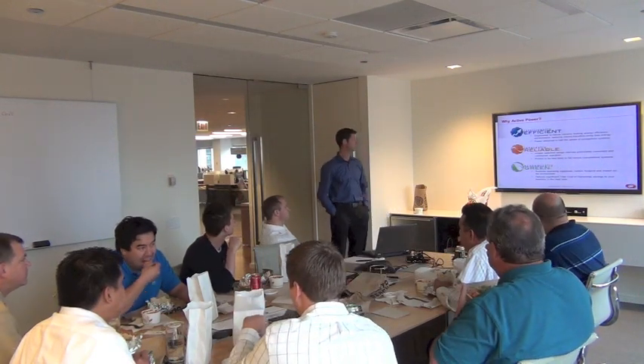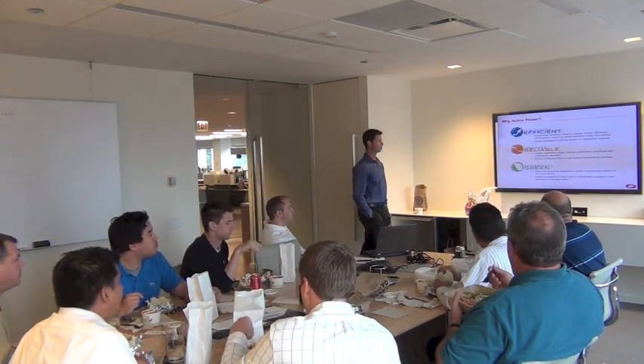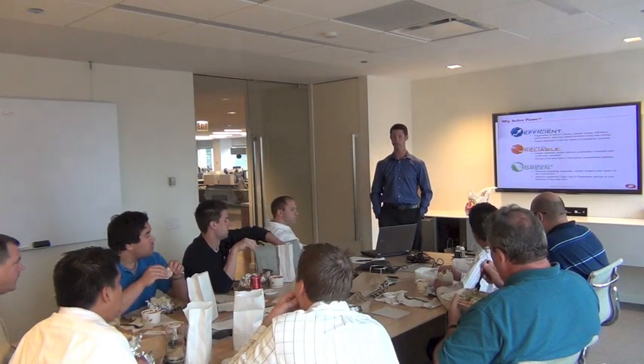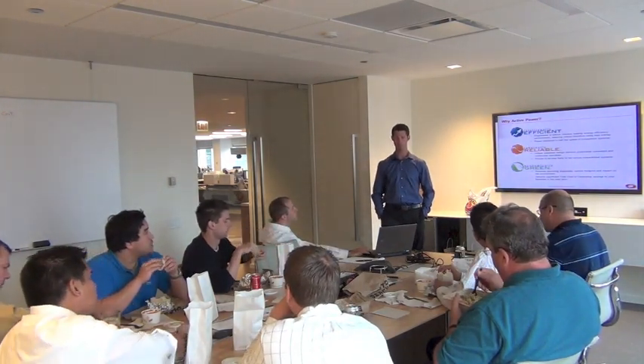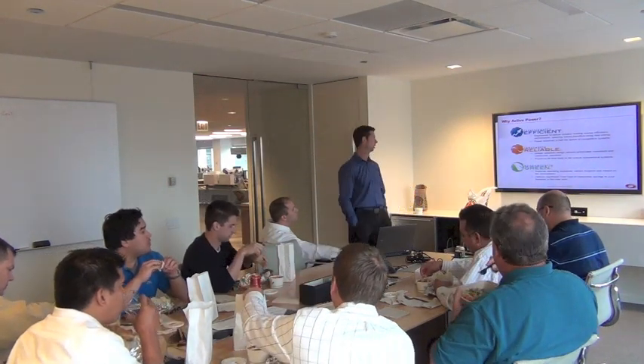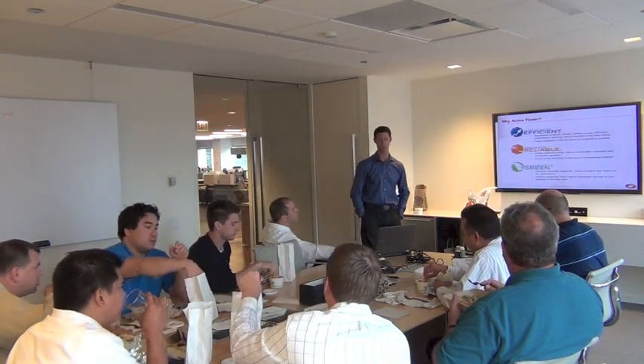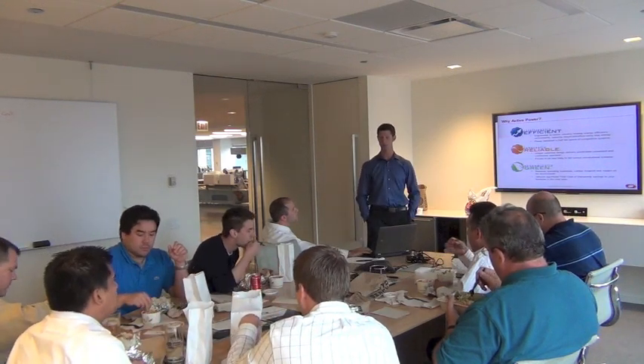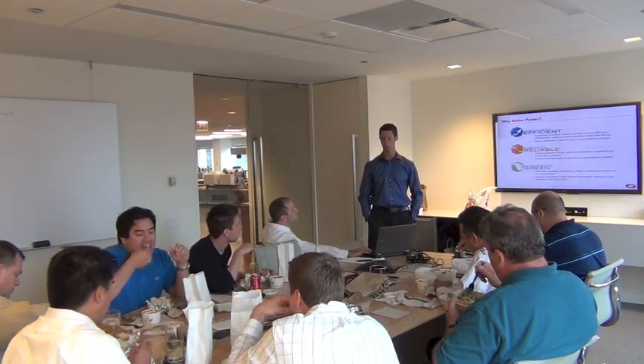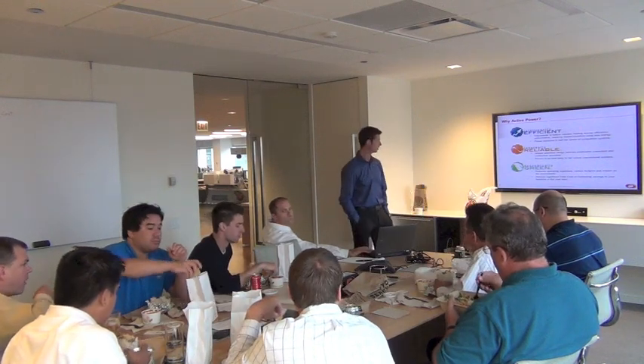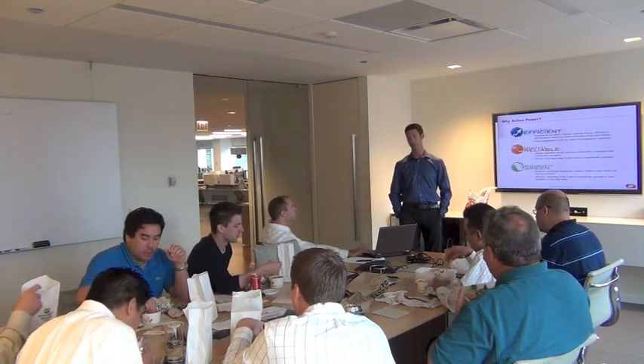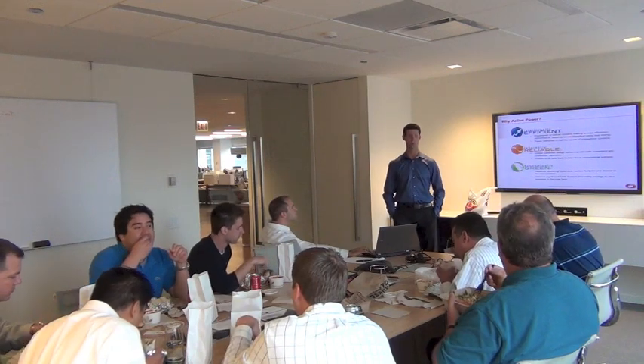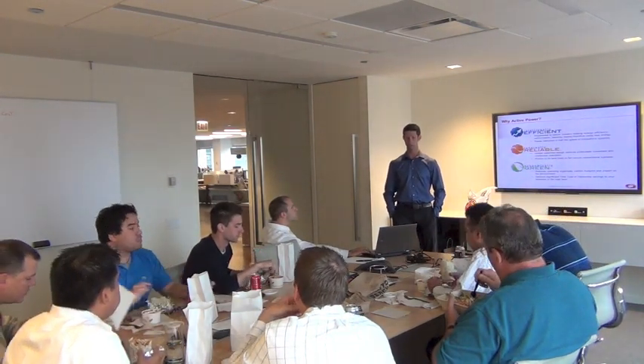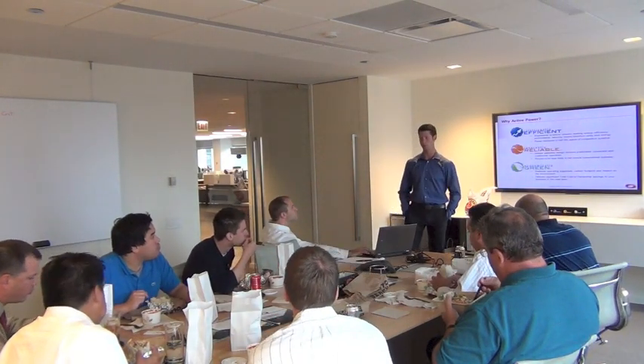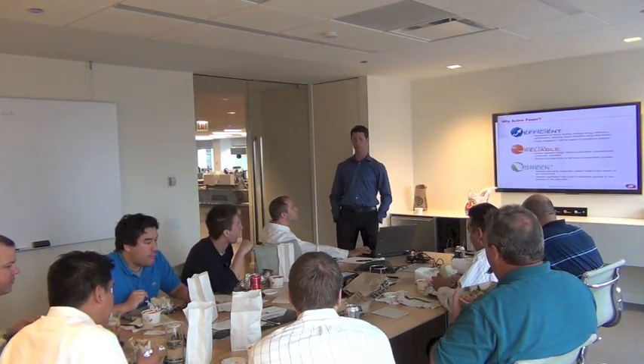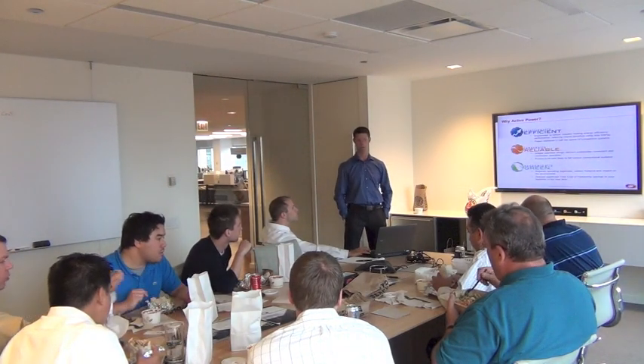Who is Active Power? Well, we're basically intelligently efficient. We're going to show how we can reduce losses with a more efficient UPS, via the nature of the flywheel system and the lower losses with the way we convert power. Inherently reliability. We've done studies showing that in the case of outages, the flywheel is 7 times less likely to fail than a battery system. Some third-party studies. And then also economically green. We definitely demonstrate a drastic carbon footprint reduction. So we're really getting a lot of industry acknowledgement right now for our green and LEED certifications, certain LEED points right out of the gate with specifying Active Power flywheel in general.